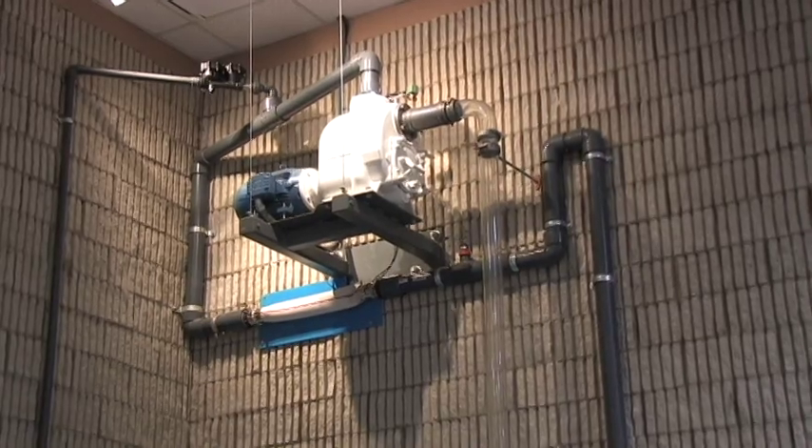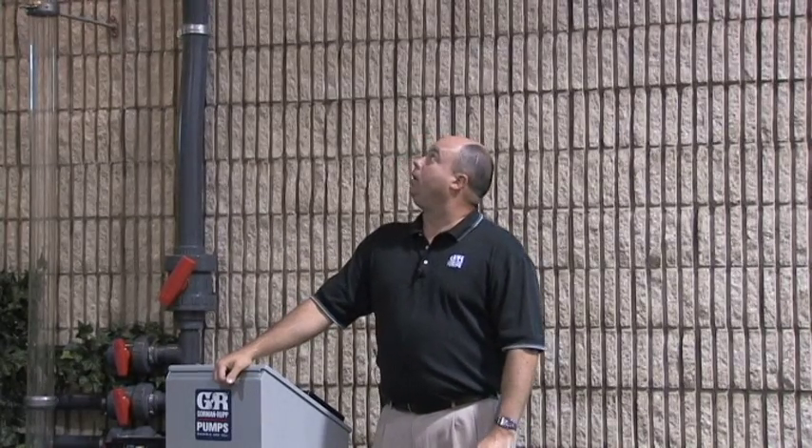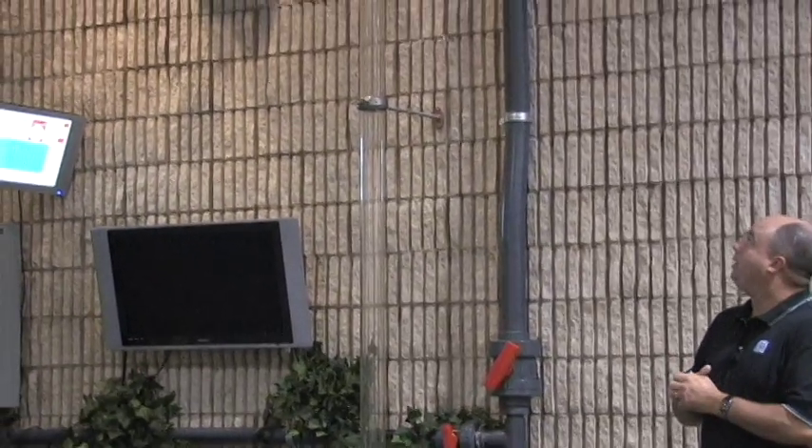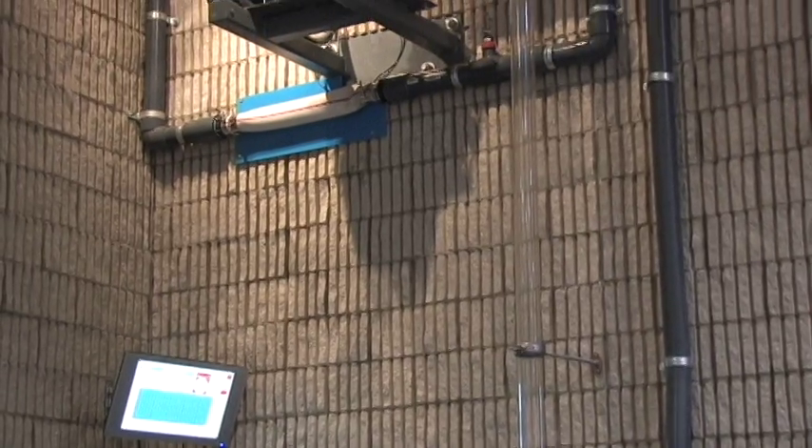Most self-priming pumps out there reference a dry prime scenario — a full pump casing and a dry suction leg — and most manufacturers will publish how long it takes that pump to prime at a given speed under those conditions. The problem with that scenario in an unattended sewage pump station application is that pumps typically don't fail like that in the field. A pump in the field will have to re-prime when the suction foot valve or discharge check valve gets held open by sticks, rags, strings, or debris, venting the system to atmosphere. When that occurs, we lose half a pump casing of liquid and drop the suction leg, and if the pump cannot get itself primed it's a service call — somebody has to go out and fill the pump up with water.